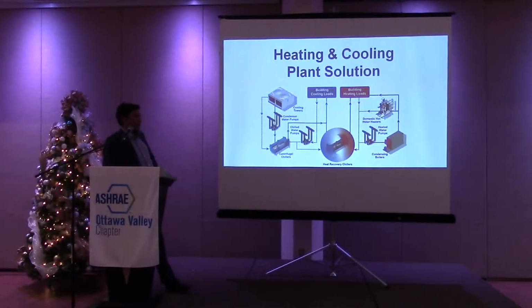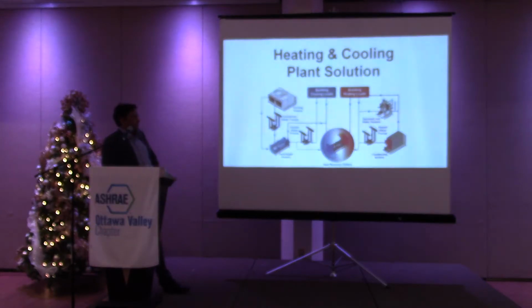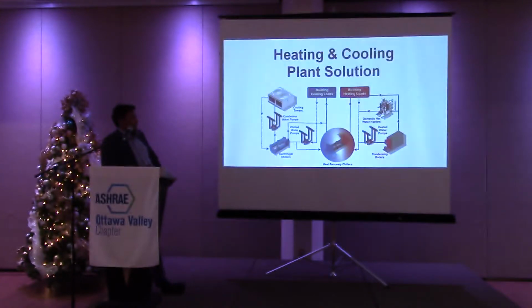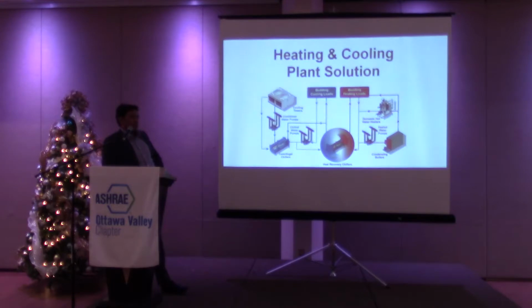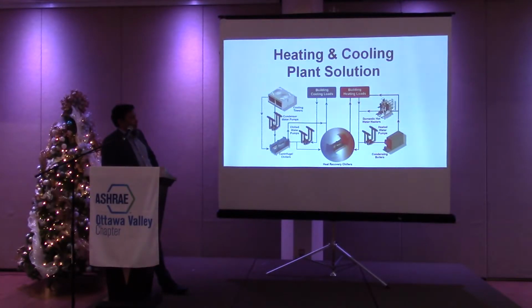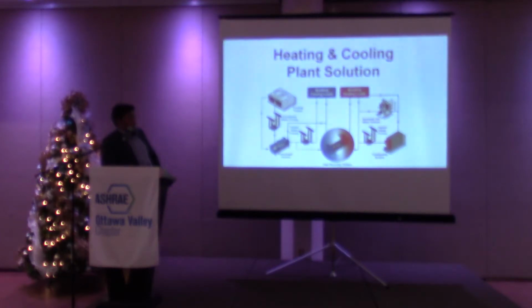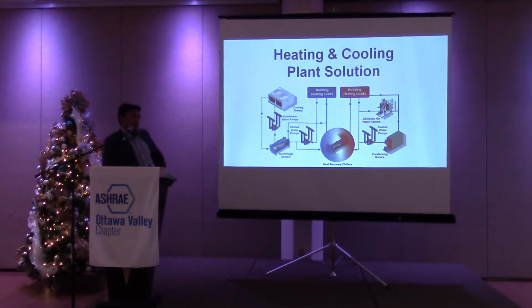So in healthcare facilities, we have what we call 24/7 cooling loads. So the MRIs, the diagnostic imaging equipment, CT scanners, communications closets, electrical rooms. There's a number of pieces of equipment that require cooling, regardless of whether it's summer or winter. And so we call those our 24/7 cooling loads. On the heating side, we always have to do reheat.